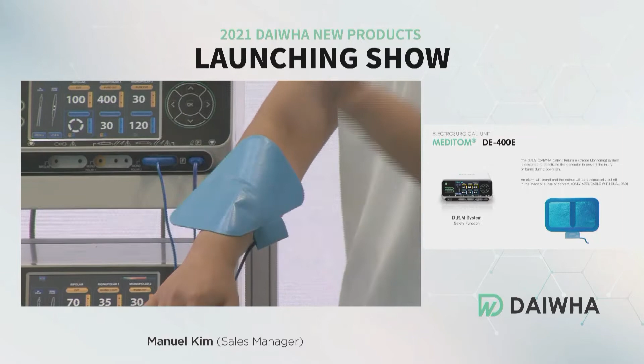Then, regarding the safety, it has DRM function, which prevents patients' burn or injuries during operation. It automatically deactivates the output in the event of loss of contact of patient return plate. It can detect the percentage of return plate attachment, and when it is under the 70%, it sounds alarm and deactivates the power output. You can see the change of percentage here.